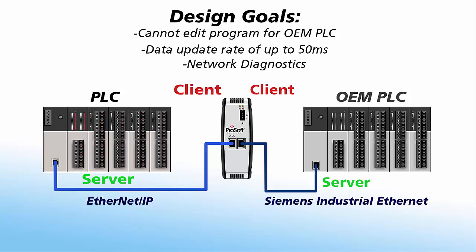However, because the gateway is initiating communications, the PLC will not have any indication in case of a communication failure. The gateway would be invisible to the PLC. So if anything goes wrong, like someone accidentally powering down the gateway, your client device will simply stop communicating. This could extend your downtime when trying to isolate the problem, especially if the problem happens five years from now when the person who programmed it is long gone. The solution that meets all the application requirements would be to set up I/O messaging between the EtherNet/IP PLC and our gateway. When PLCs do I/O messaging — sometimes called an I/O connection — they require a communication update interval to be set. This will ensure the communications between the PLC and gateway are fast and consistent, as they will be given priority over other communications.